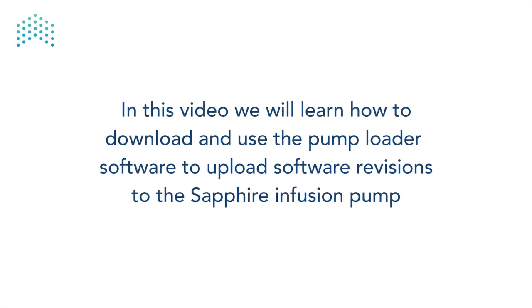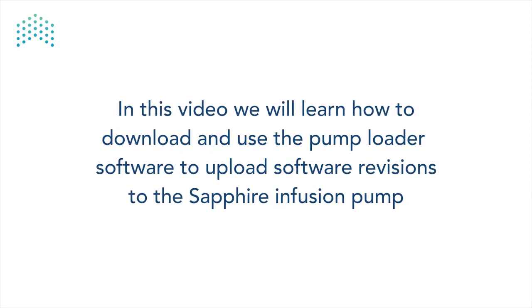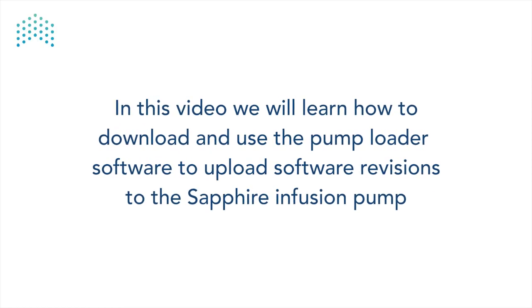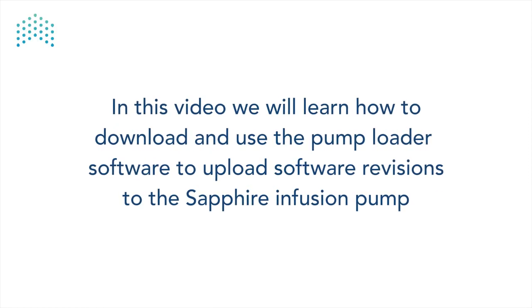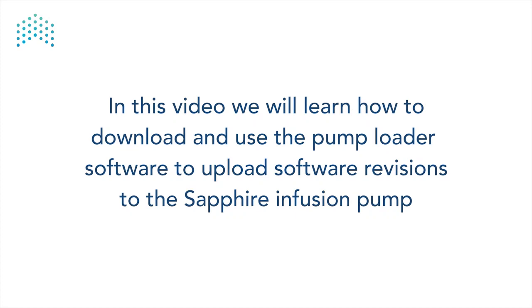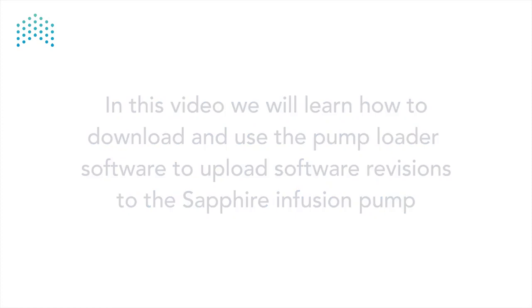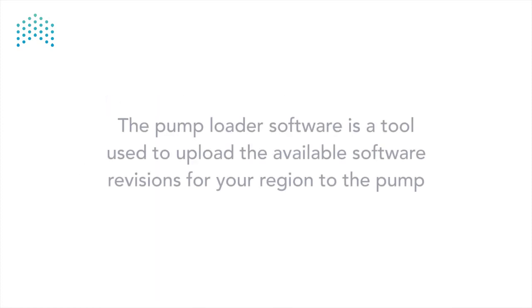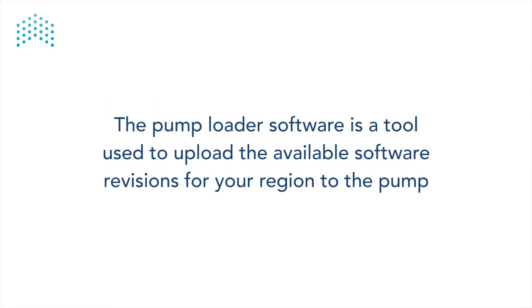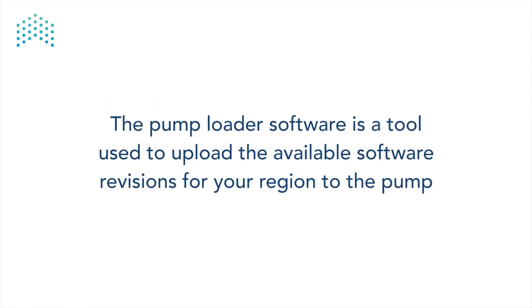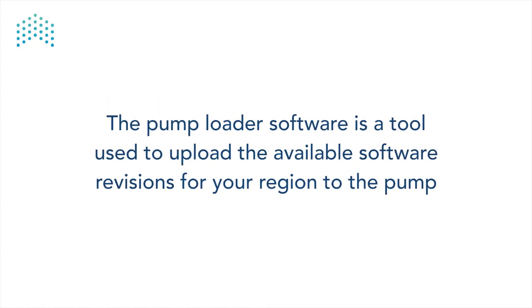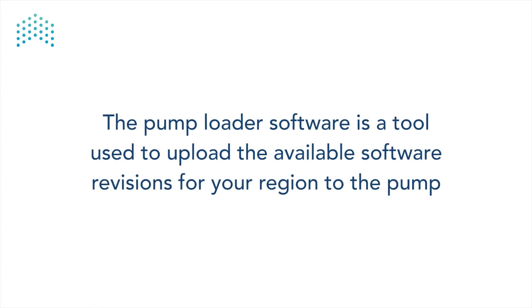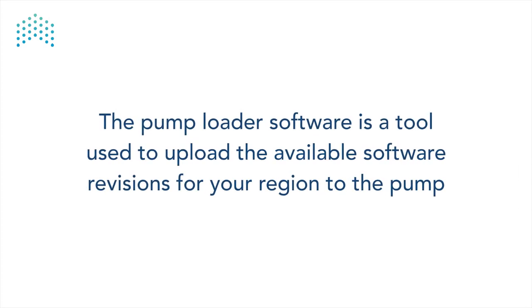We will learn how to download and use the pump loader software to upload software revisions to the Sapphire Infusion pump. The pump loader software is a tool used to upload the available software revisions for your region to the pump.